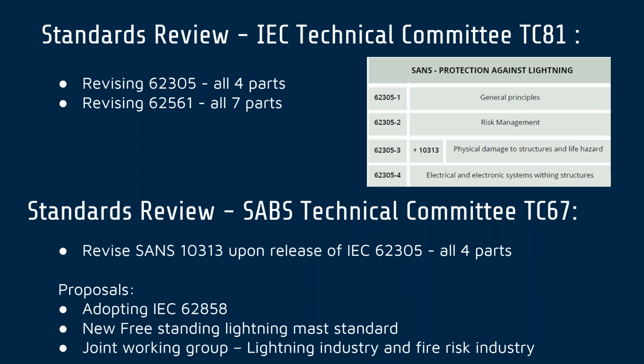So, for your reference later and for the audio record, all the SANS standards related to the IEC standards for lightning protection are all being revised right now. So please understand what is coming is going to be a lot of changes. SANS 10313 is going to be changing, but it's got to change in relation to 62305. IEC 62858 needs to be adopted in South Africa - we'll find out about that on Tuesday. We're proposing a new freestanding lightning mast standard, as well as a joint working group between the lightning industry and the fire risk industry. And then there is one standard that is not actually a standard yet, South African Technical Specification 62561 Part 8. It is not a South African standard yet, and at the IEC level it is not going to be approved as an international standard yet either.